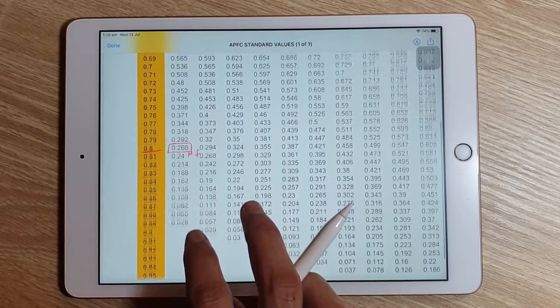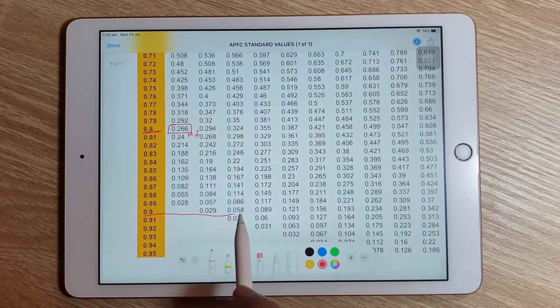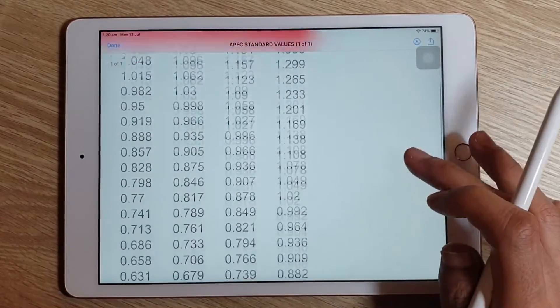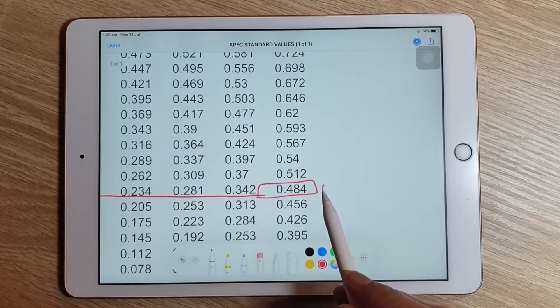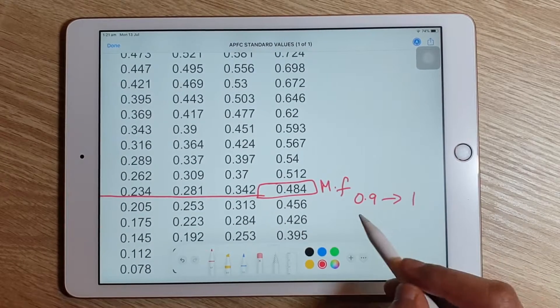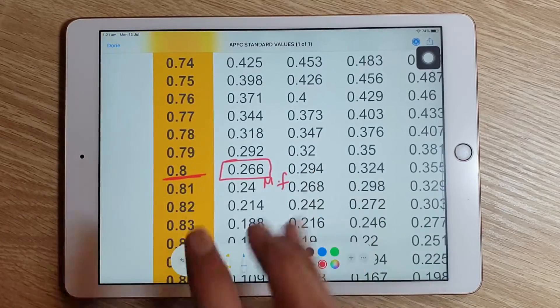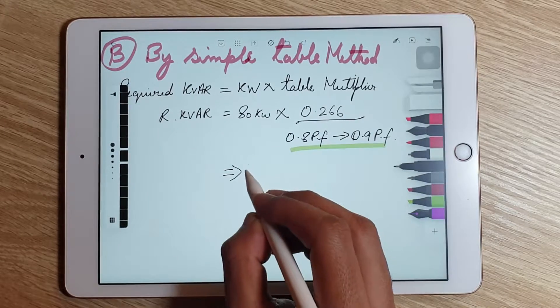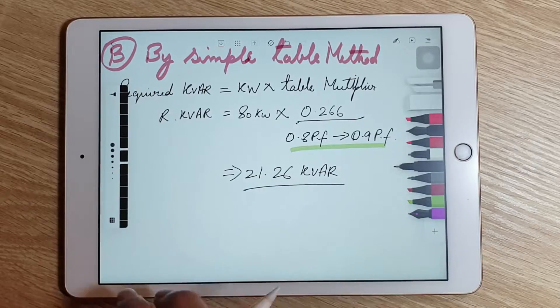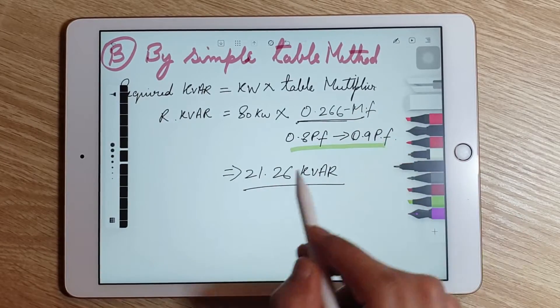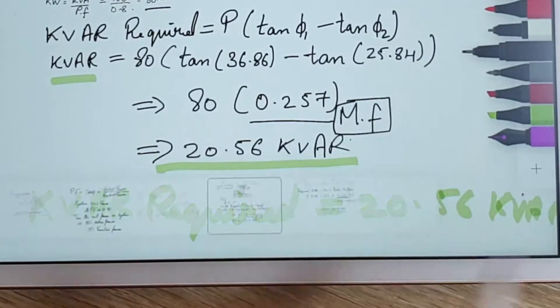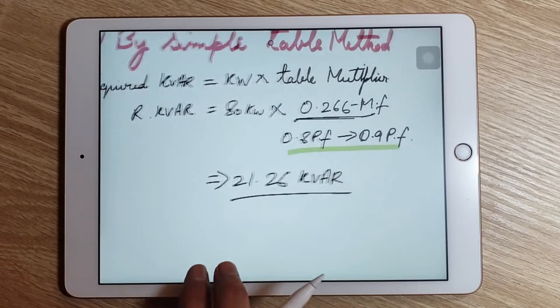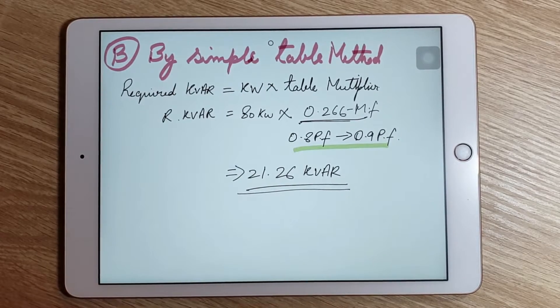Similarly, if the measured power factor is 0.9 and the required power factor is 1.0, we trace those values in the table to get a multiplying factor of 0.484. In our case, going from 0.8 to 0.9, the multiplying factor is 0.266, giving a required KVAR of 21.26. Comparing with the first method, which gave a multiplying factor of 0.257 and 20.56 KVAR, the results are approximately similar with no significant difference.